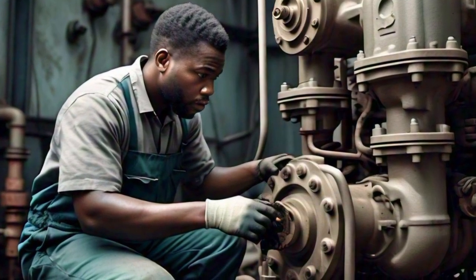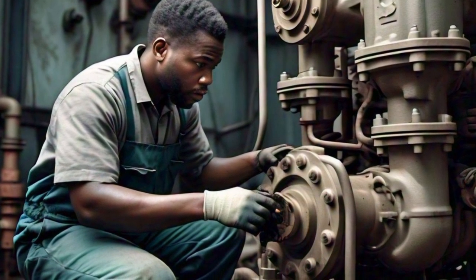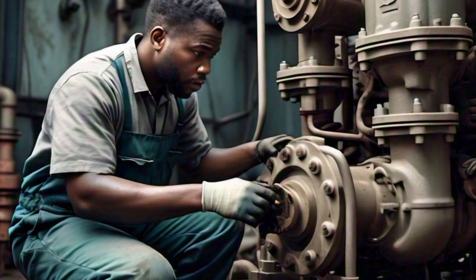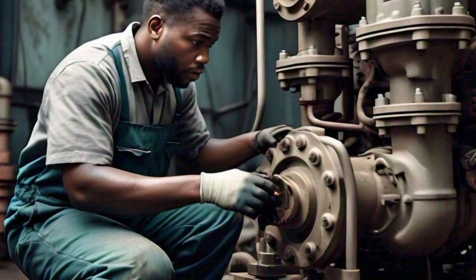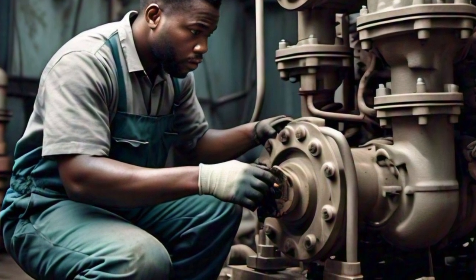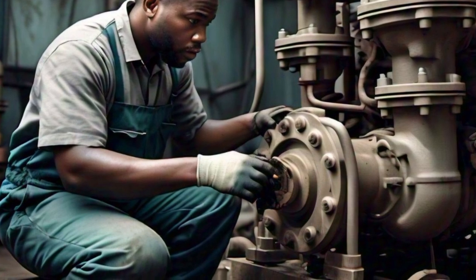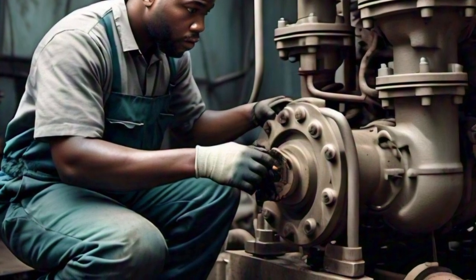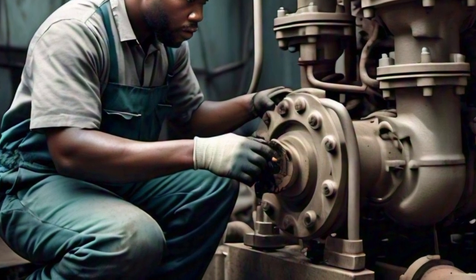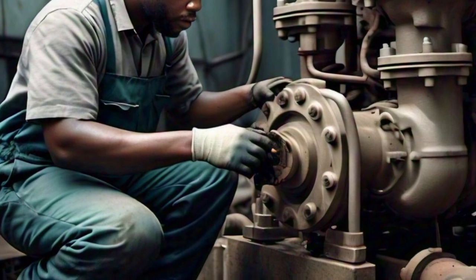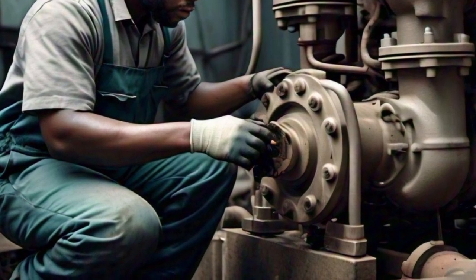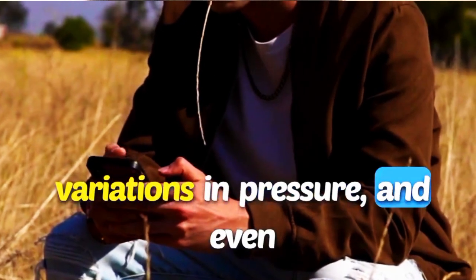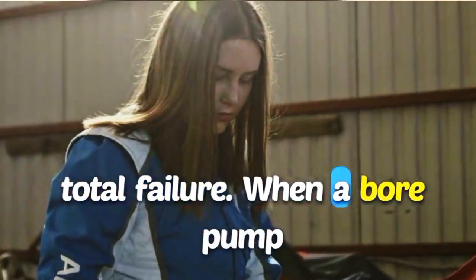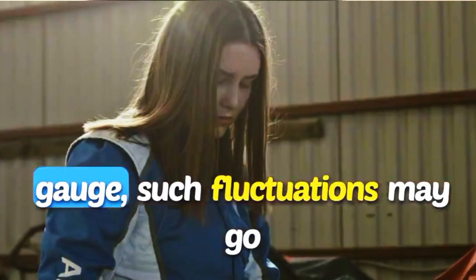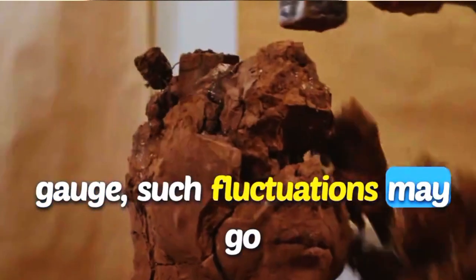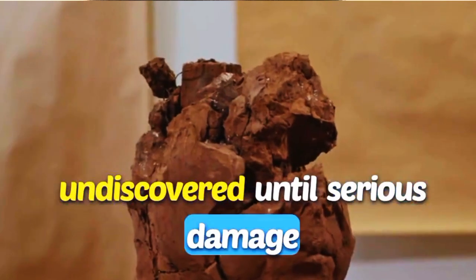Number 5. Unmonitored modifications to pumping conditions. If the pump application changes, it will most likely result in a changed pumping condition, although a well-chosen pump will normally provide many years of good service. As a result, the pump would attempt to run at a less than ideal level, which could lead to decreased flow, variations in pressure, and even total failure. When a bore pump operator does not use a pressure gauge, such fluctuations may go undiscovered until serious damage has occurred.